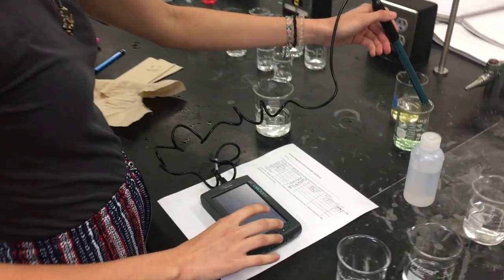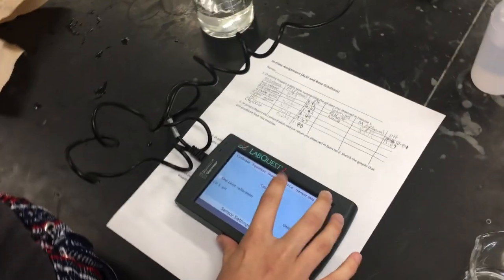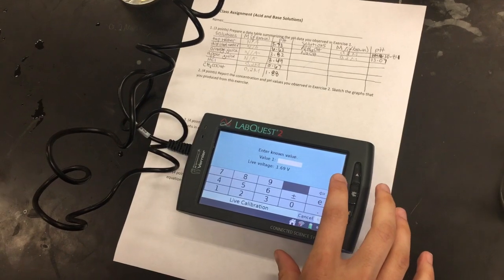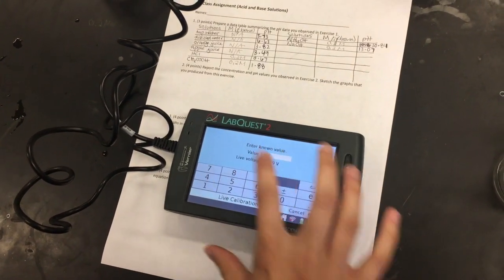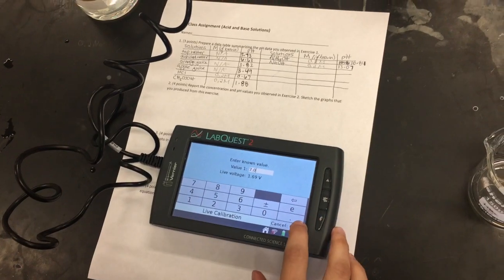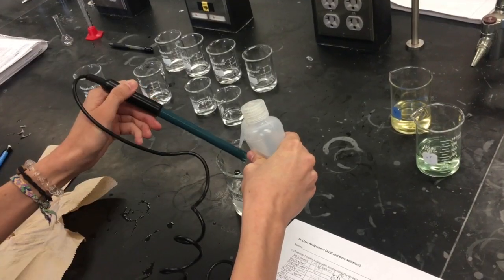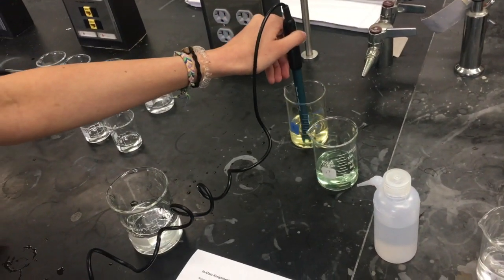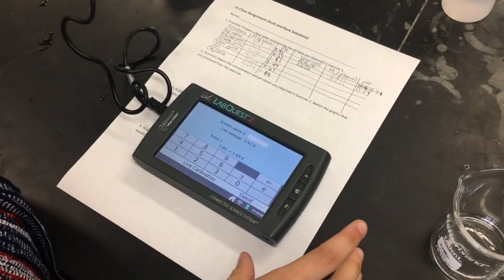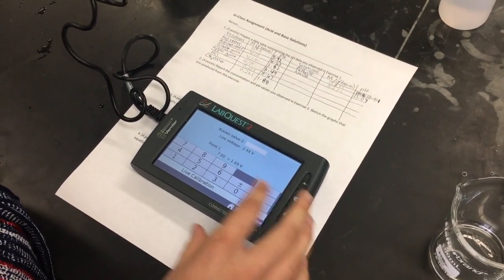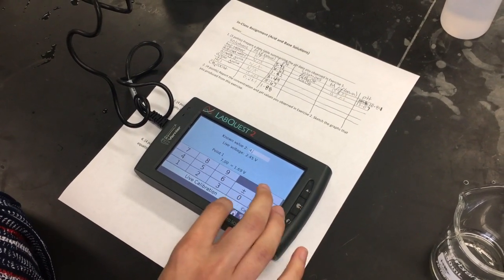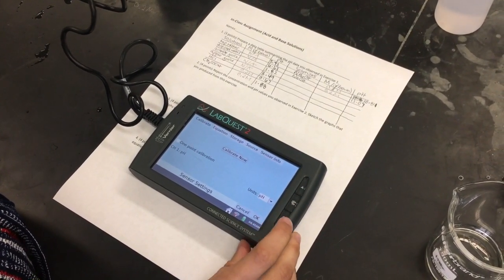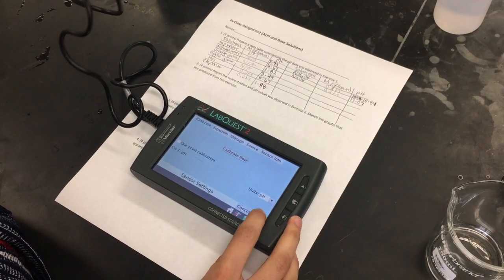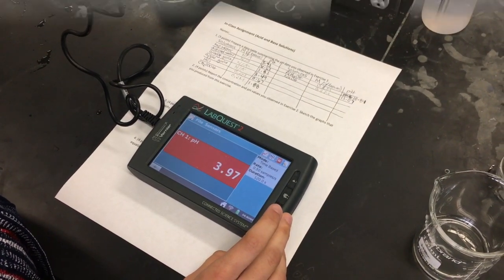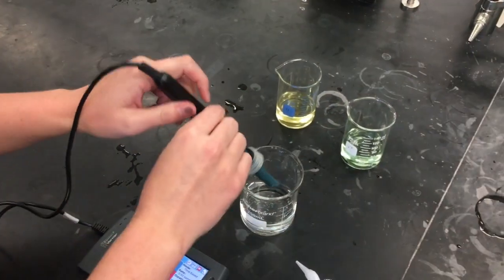Here, I perform the 2-point calibration method with a better view of the screen, so I click Calibrate Now and then wait for the live voltage to stabilize and then type in 7.0 as it's in the pH 7 buffer. Between point 1 and point 2 of the calibration method, it's important to clean the pH meter before putting it in the pH 4 buffer solution. Then, I wait for the live voltage here to stabilize and type in 4.0 as it's a pH 4 buffer solution. Then, the meter should be calibrated. 3.97 is very close to pH 4.